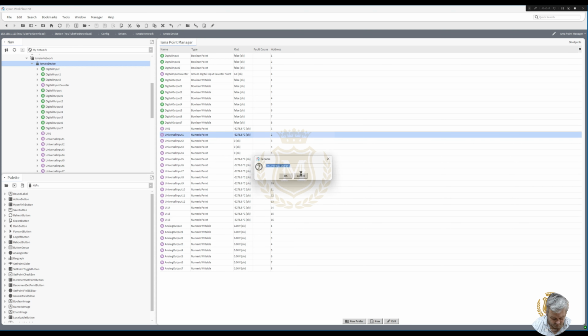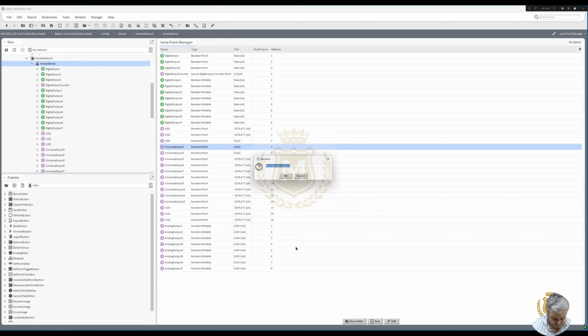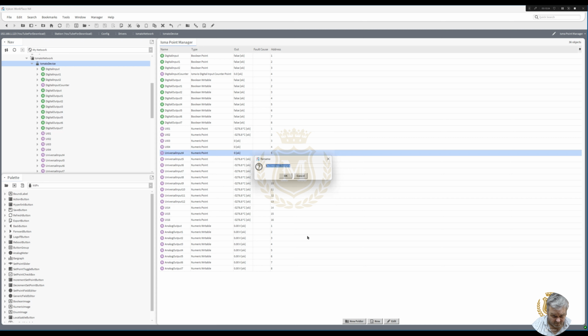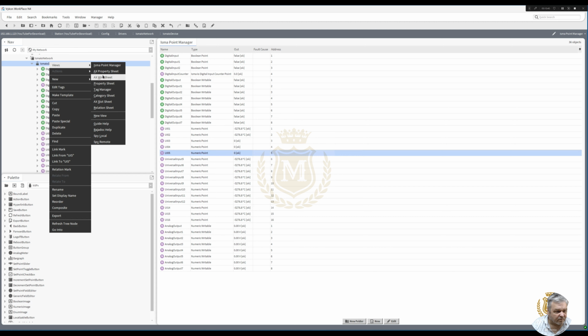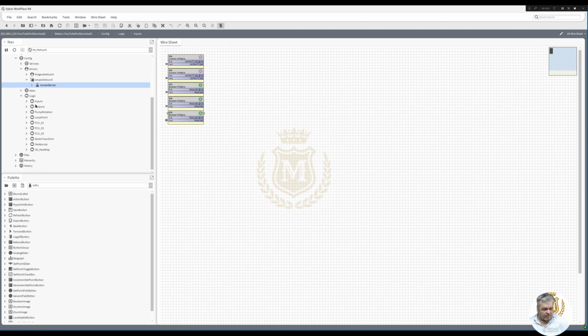Rename. UI2, rename. UI3, rename. UI4, rename. UI5, views, wire sheet. So if I take UI5 there and double click it, that takes me to UI5 on my sheet there. So that's my input sheet done, and then my outputs, I'm using AO1, AO2 and DO1, DO2, DO3.